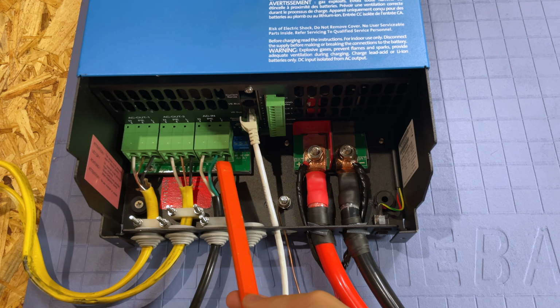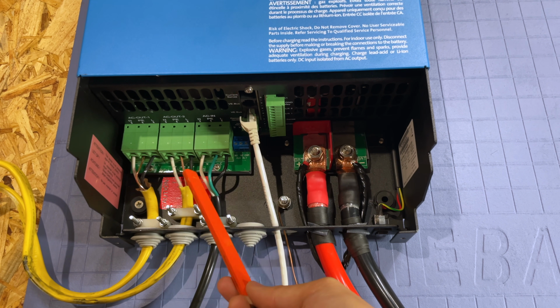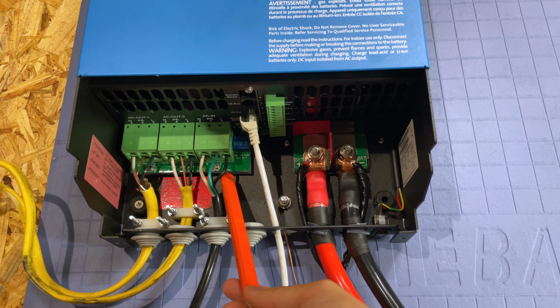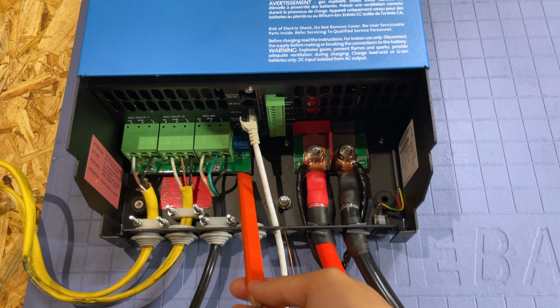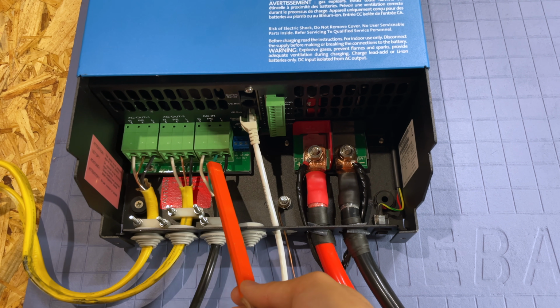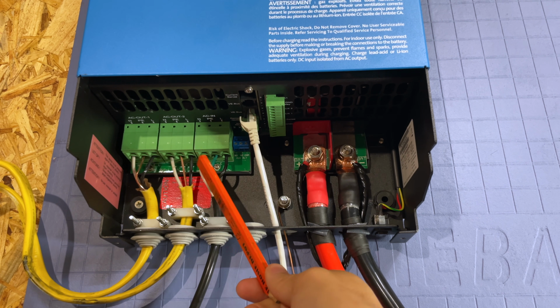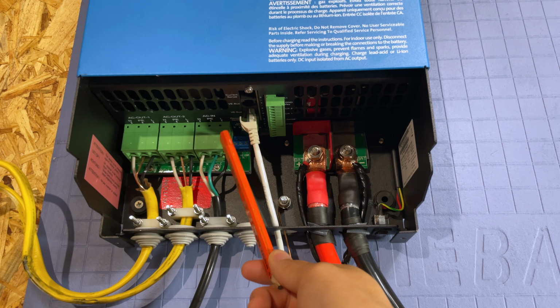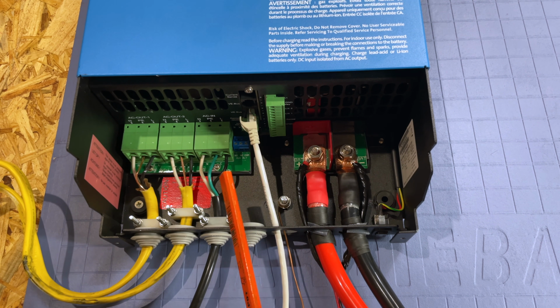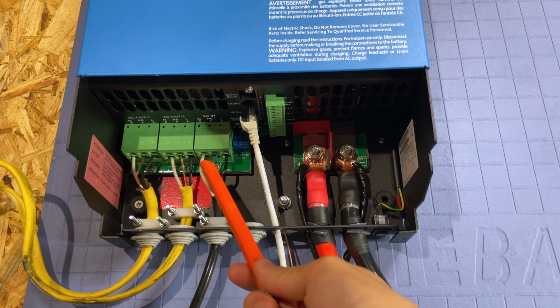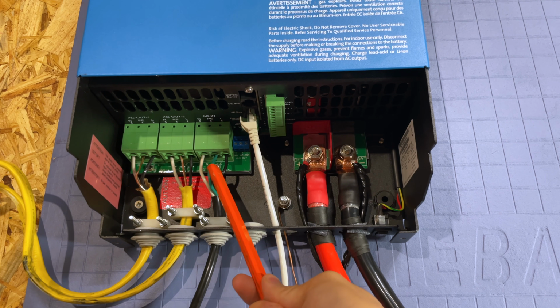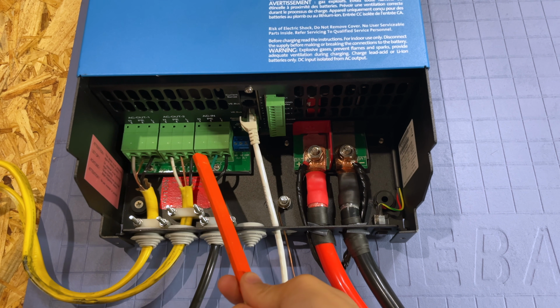The second thing I'll note on here is that this wire here is severely undersized, but this is the wire that I just found right here on hand. I crimped ferrules on there and put it in here. But this, I believe, is like a 16 or maybe 14 gauge wire. And you put ferrules on here because this is pretty thin stranded, and you put it into the AC in, and there's a cord so you can plug it into the wall in case you need to, right? But even though it is undersized, you can go into the settings and set the maximum AC in current.